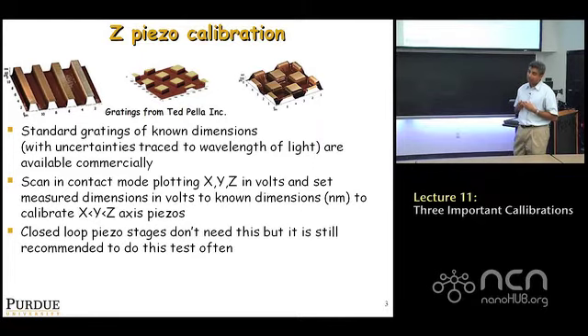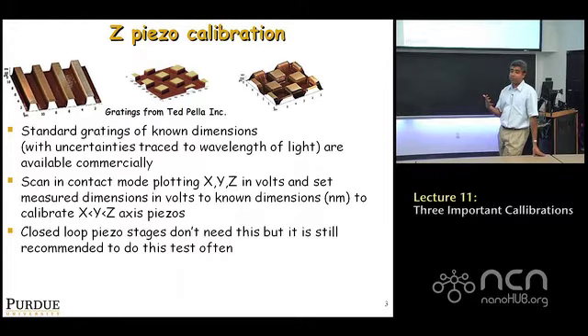So when you buy the grating, they're going to tell you the grating has a certain height of, let's say, 10 nanometers, plus or minus, and they give you an uncertainty with it. And I highly encourage you, if you buy it from a manufacturer, if you pay a little extra, you actually get a certificate which quantifies the uncertainty associated with it, because people can quantify the uncertainty to within the wavelength of light. So it's a traceable standard.